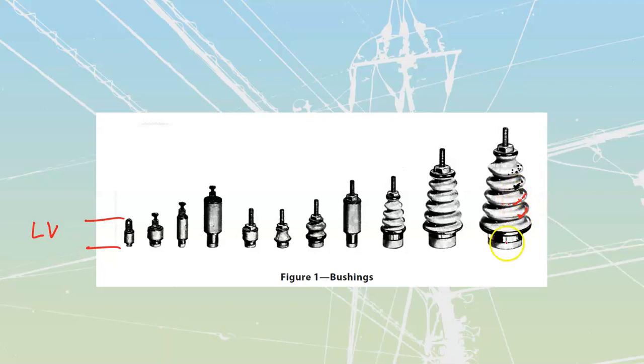The dust is something we're going to be able to track through. We don't want any sort of tracking surface on high voltage, because then we have danger of flashover, where an arc strikes all the way across from our line down to our grounded can, since we're mounting these inside a grounded can. We prevent that through length, skirting, and keeping all of our insulation clean afterwards.